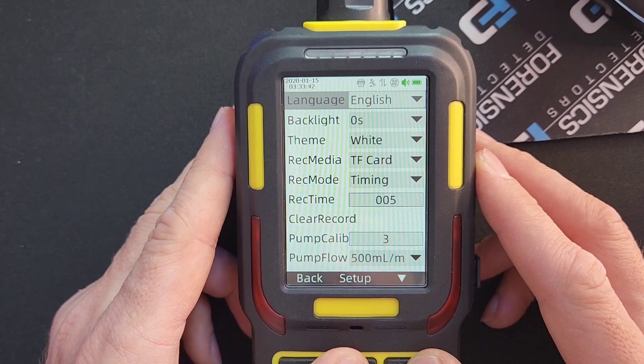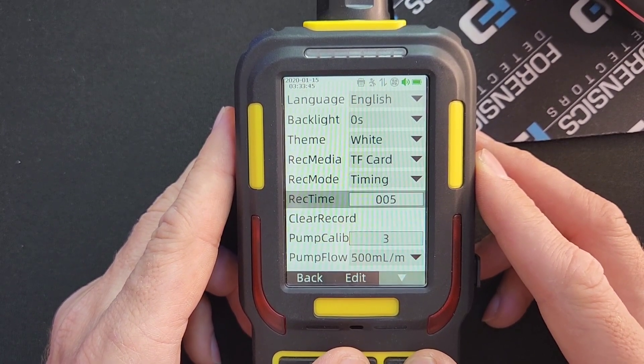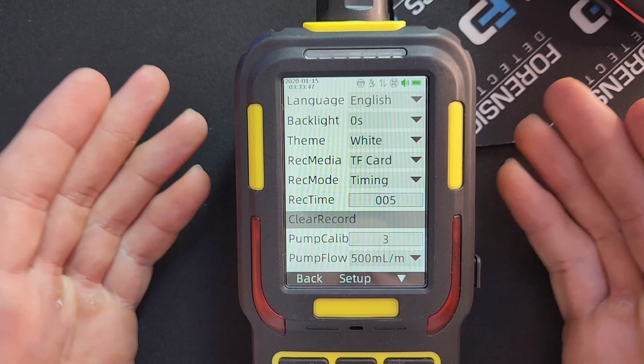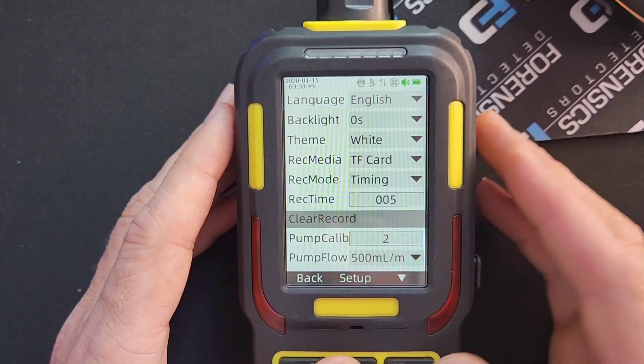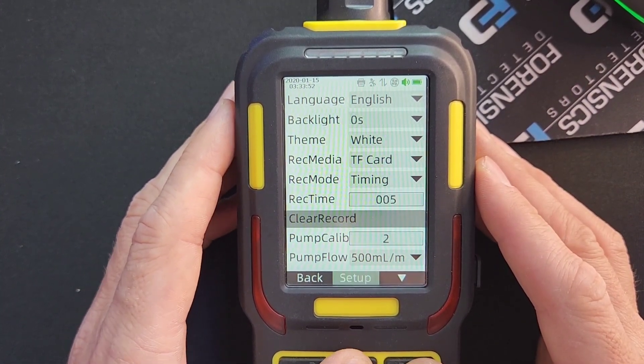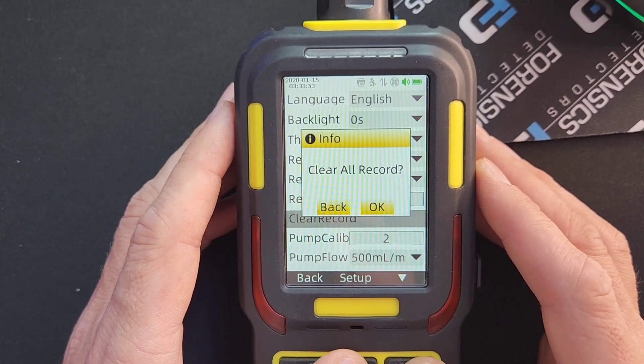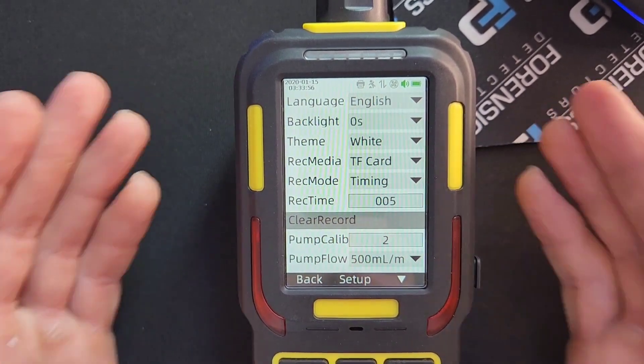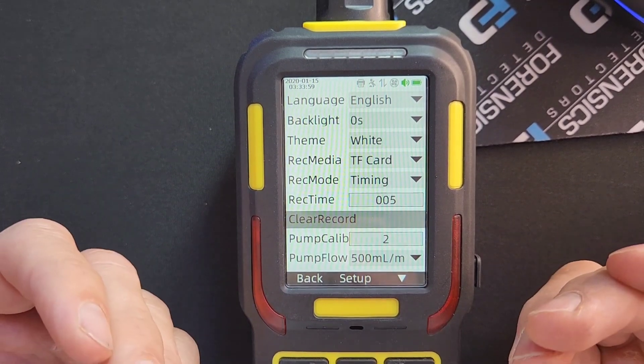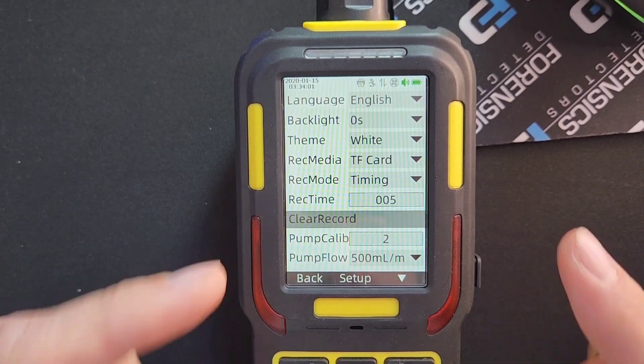System Set controls how we data log. The first thing we're going to do is assume we want to start fresh, so we're going to delete all previously logged data. Go to Clear Data, go to Setup, press down, press OK — and bang, clear success. We have cleared all the data from memory.